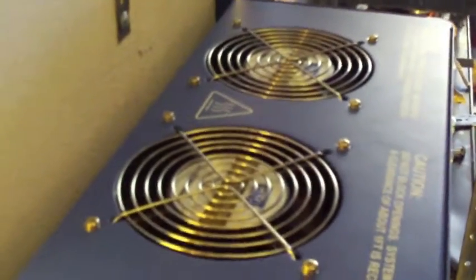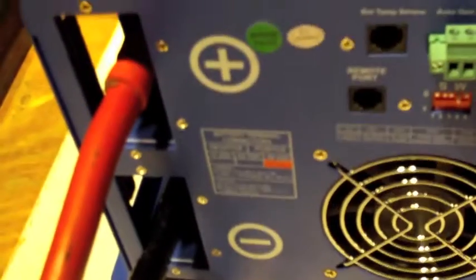This is the front. Here on the side is where the battery power is connected into it. There's a plate that goes over the front of that and I have the plate off. There's vent holes on both sides and on the top there are two fans — one's a DC and one's an AC fan, cooling fans. Here on the bottom you have a DC cooling fan. There's your DC going into it, 48 volts.